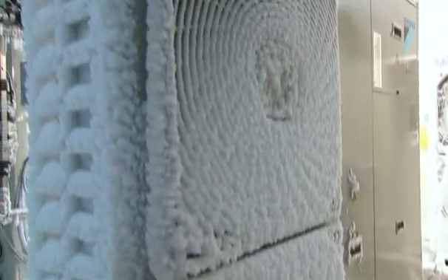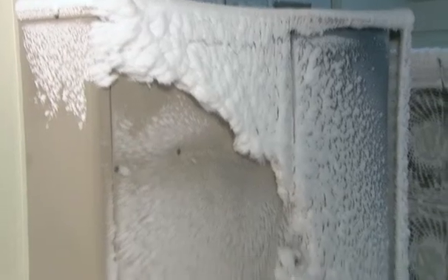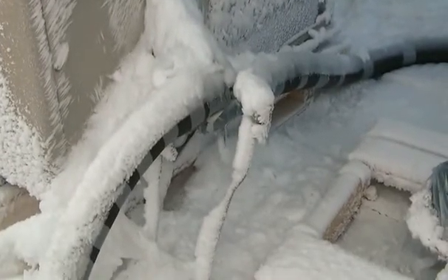It withstands a power cut of three hours in extreme conditions of minus 20 degrees Celsius and a humidity of 70%. By adding an external fan to the test room setup, our technicians were even able to simulate wind blowing at a velocity of 3 meters per second. We monitored the temperature in the water piping during the entire test to check that it remained above 2 degrees Celsius.